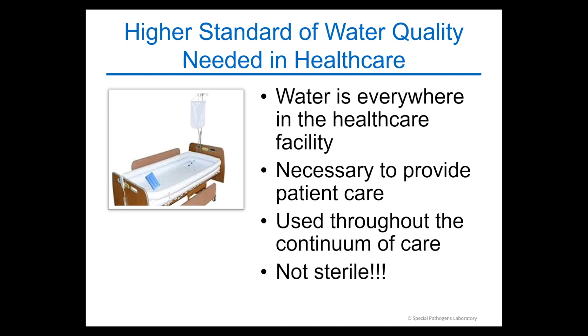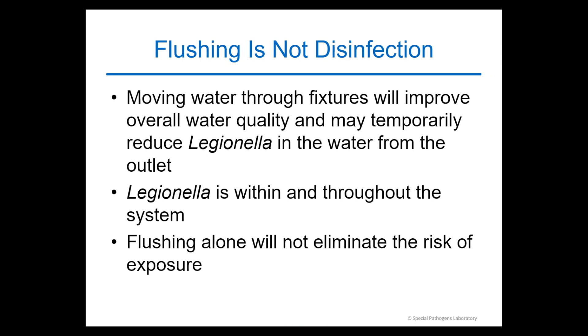I talked a little bit about disinfection and controlling organisms - what do people do? I want to tell you that flushing your fixtures is not disinfection. Moving water through fixtures is a good idea, temporarily reduces the organisms coming through the fixture, but doesn't do anything to remove them from the biofilm up through the fixture. So it improves overall hygienic quality of the water, but Legionella and these other pathogens are within and throughout the system. Flushing alone will not eliminate them.